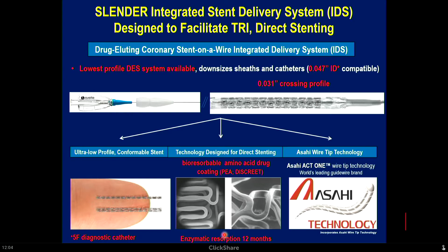The 2.5 stent is a 0.031 inch crossing profile. The 3.0 is 0.032 inch. This is less than the caliber of the wires we use for vascular access. It'll fit comfortably in a 5 French diagnostic catheter, doesn't really need a guide, and the polymer is a unique amino acid composite called PEA that undergoes enzymatic erosion over 12 months, not hydrolysis like the PLA derivatives.